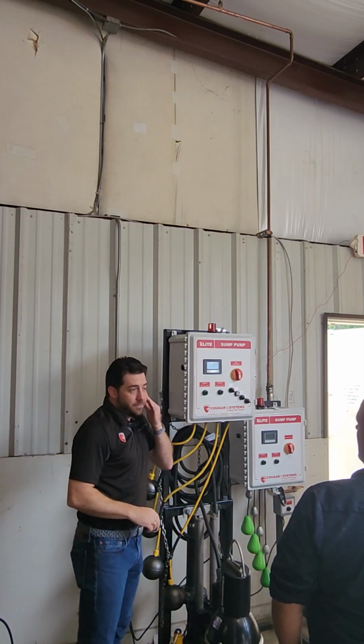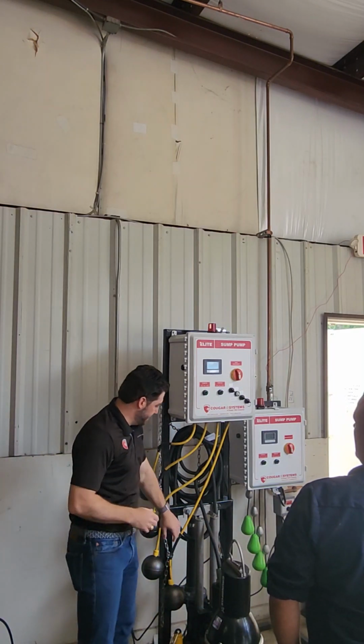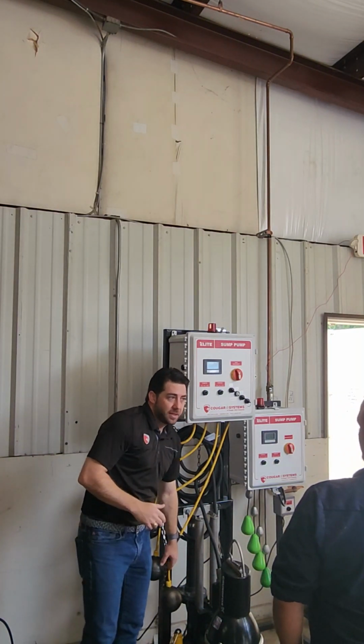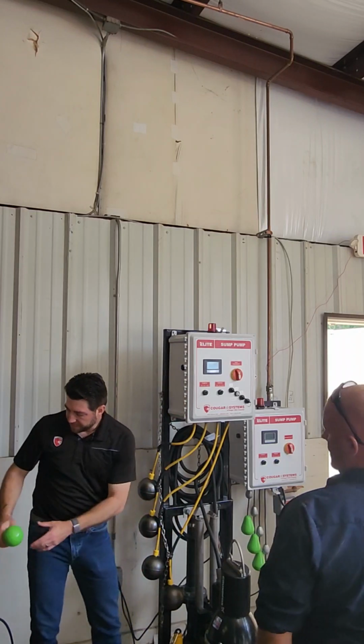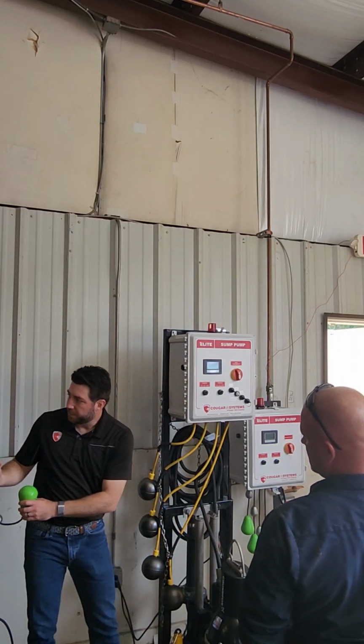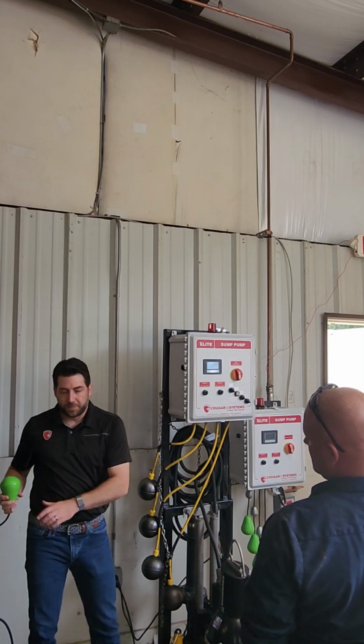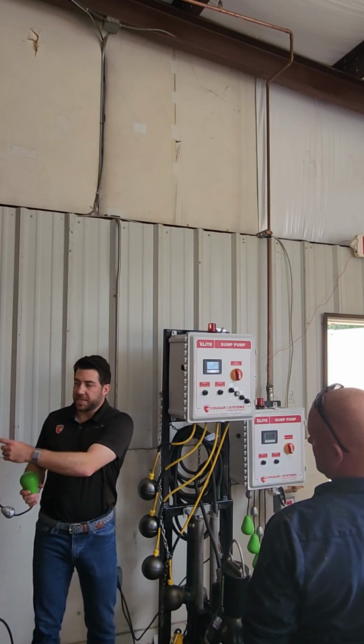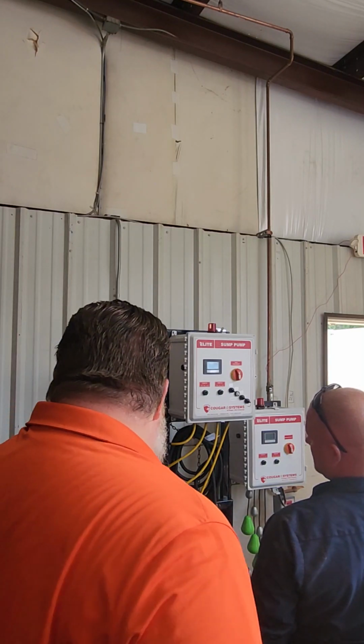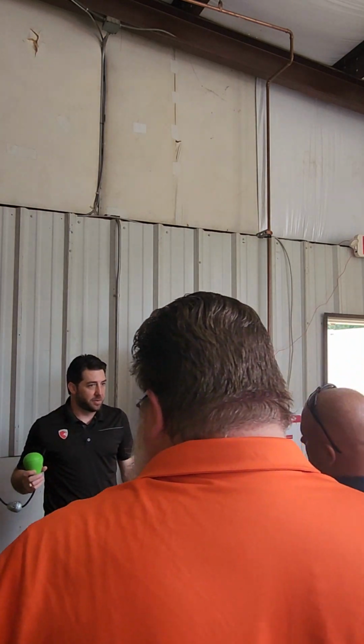The runtime alarm. This is to protect against the bottom float switch failing. So we talked about if you go through this sequence here and this pump comes on and it just hangs up like this, there's nothing to turn it off if it's pumped down, and the only thing that's going to protect it is the thermal overload inside the pump.